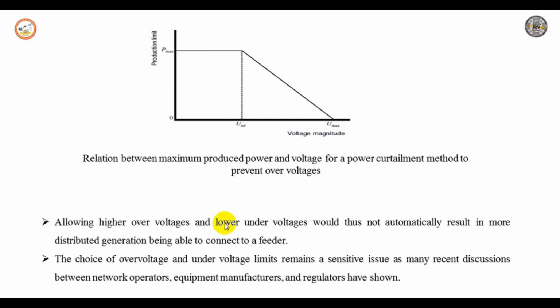So only local measurement parameters are used, so there is no communication between generation units or a central controller needed. Whenever the voltage at the point of connection exceeds the value U reference, the power production will be limited. The second voltage threshold is U max, where the power generation could be reduced to 0.